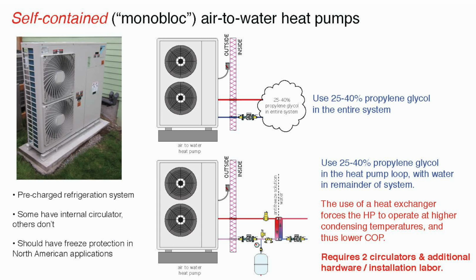You can set them up, typically, with antifreeze. Most manufacturers are going to mandate the use of antifreeze because if we have water in an outside unit, obviously in a long-term power outage, it could freeze. You can either set up the whole system with antifreeze or you can put a heat exchanger between the heat pump and the balance of the system. I would recommend the first one, the top one. Put antifreeze in the whole system.